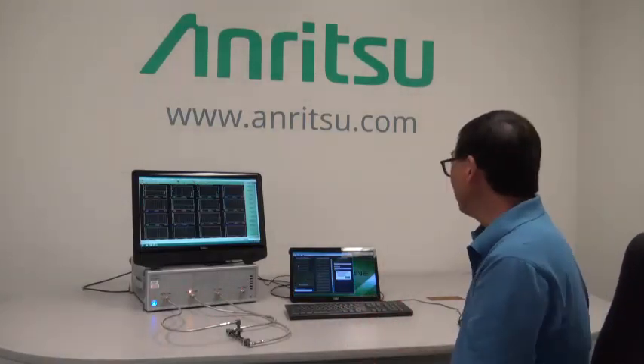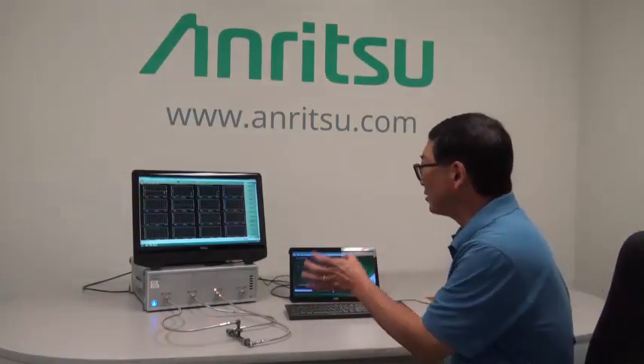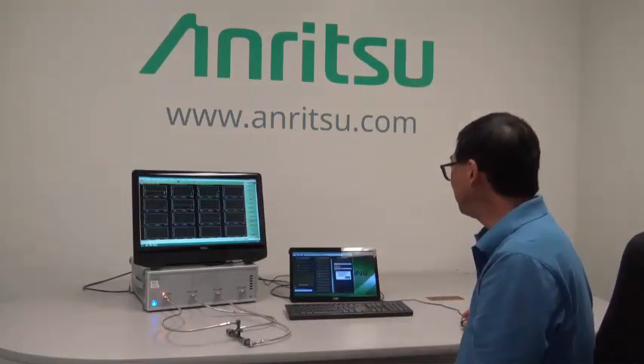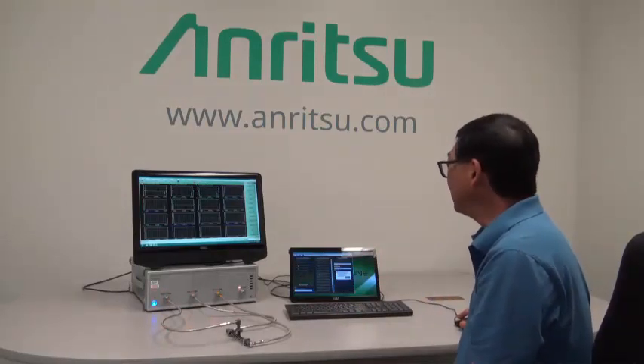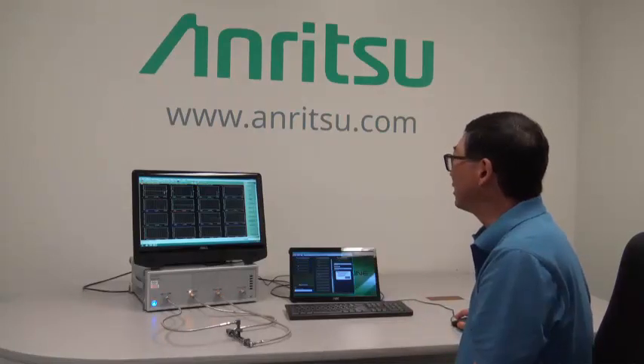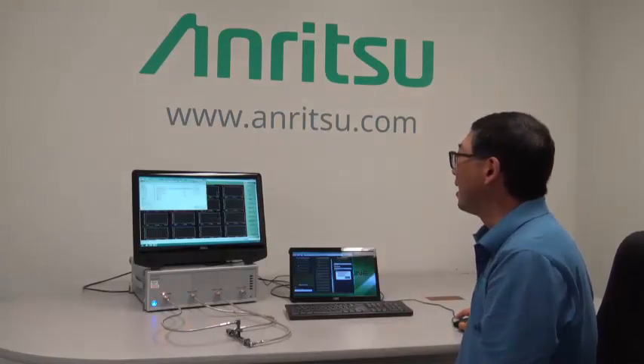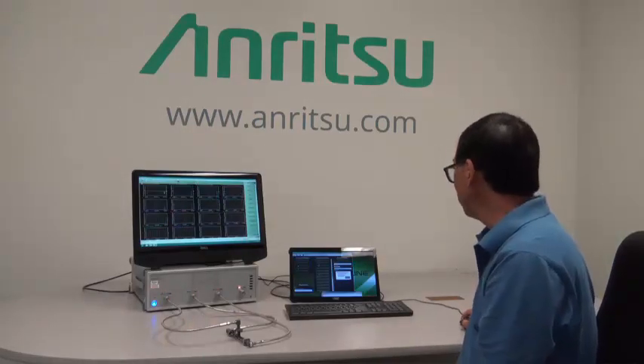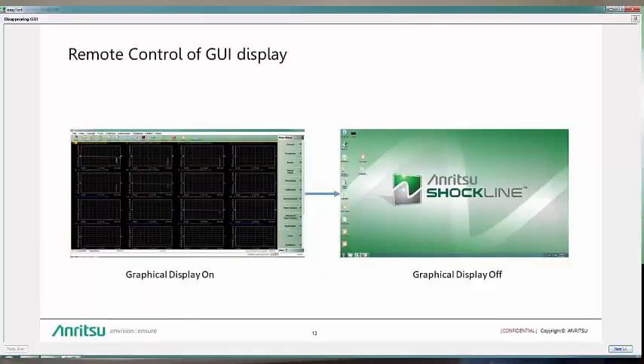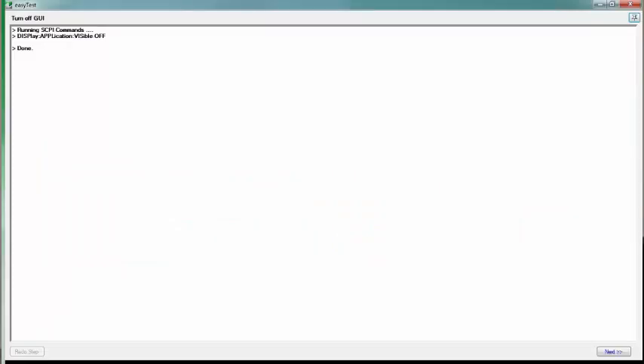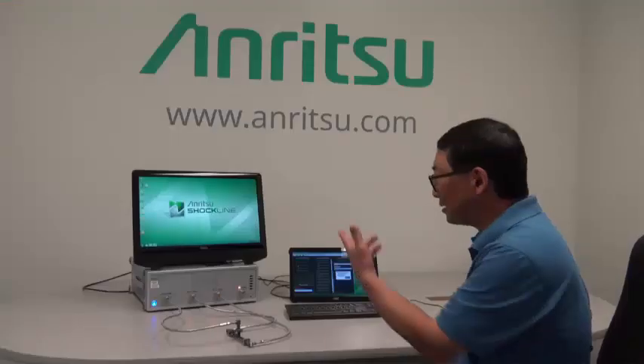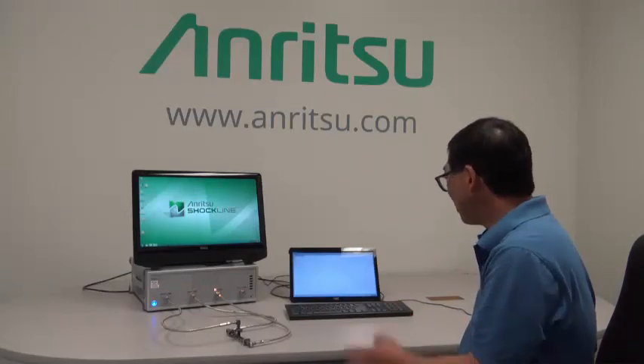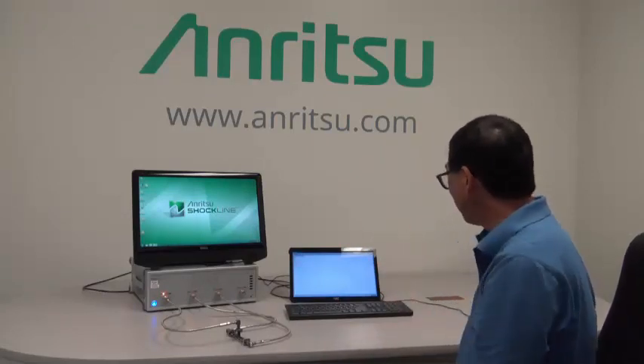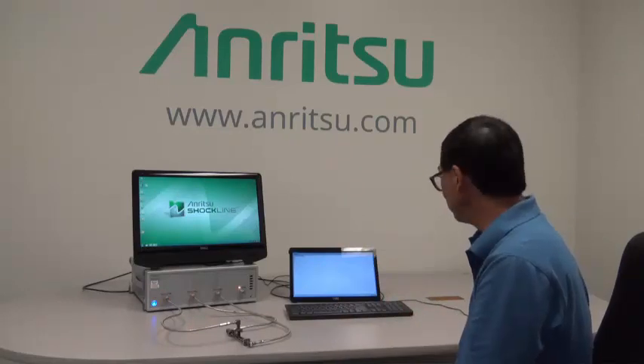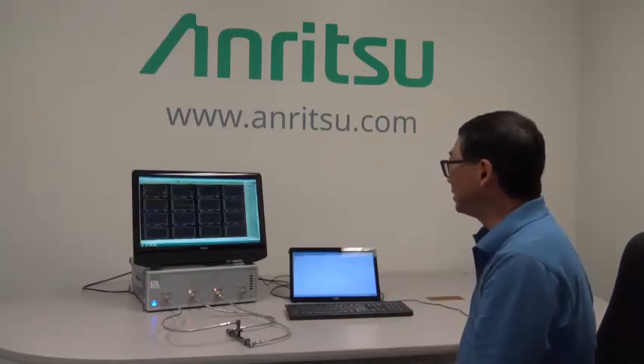One last thing, if you don't want the user to have interaction capability with the GUI, we do have the ability to remotely turn off the GUI. So if we go ahead and run that easyTest script real quick, I have the ability to turn off the GUI, and we'll just show that here. We'll run a SCPI command which turns off the GUI, and so the user no longer has the ability to bring up the GUI, and you can run the rest of the commands through easyTest and have no interaction from the user. We can turn it back on remotely as well.